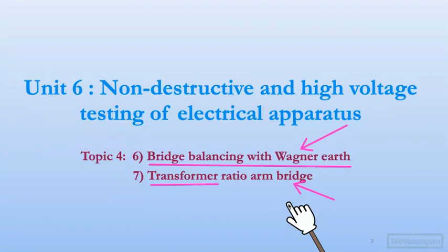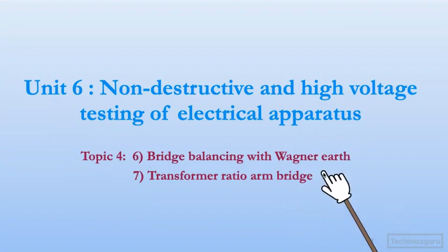Again, I must emphasize and help you understand that all these variations are because of the presence of some nearby ground objects or ground capacitances that we would like to eliminate from the bridge balancing equation because they will cause error. If any other capacitance is present other than the one which you want to measure, because ground capacitances are invisible, they have to be eliminated. The error due to ground capacitances has to be eliminated through proper design and care and proper evaluation of the various objects nearby.